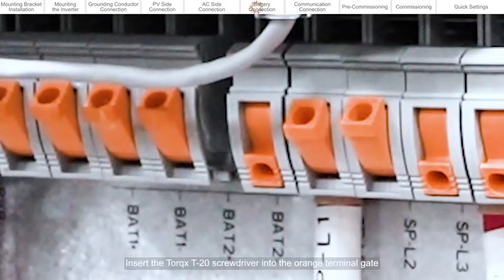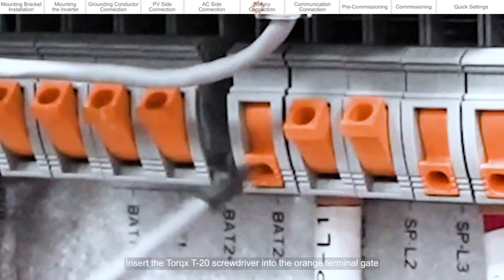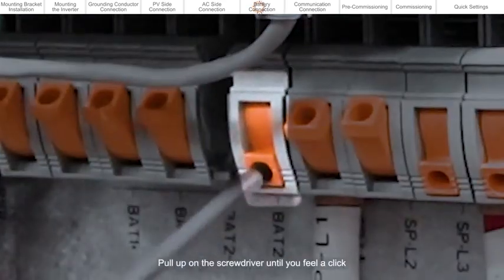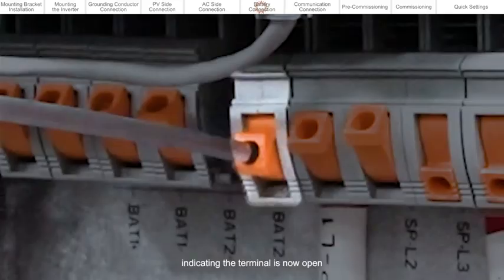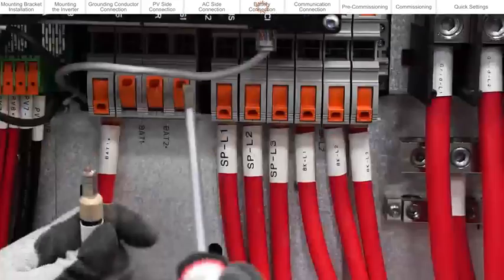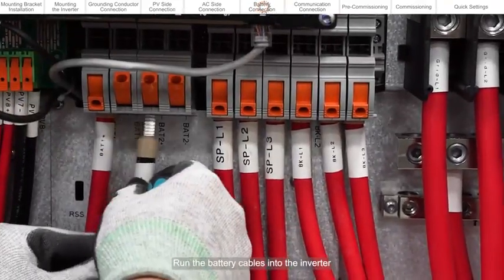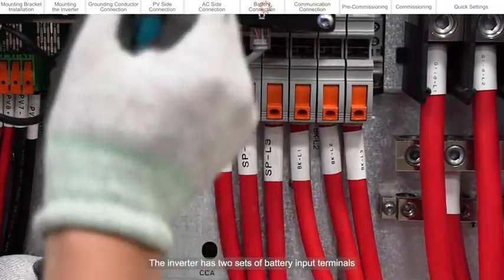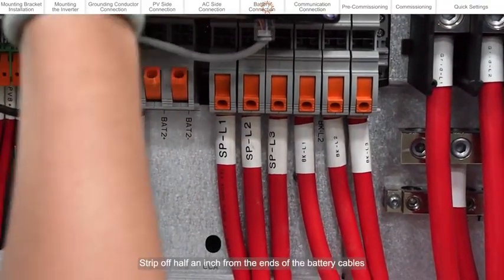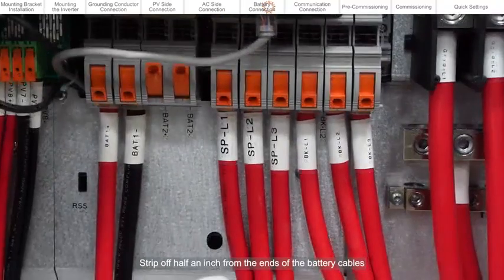Insert the Torx T20 screwdriver into the orange terminal gate. Pull up on the screwdriver until you feel a click, indicating the terminal is now open. Run the battery cables into the inverter. The inverter has two sets of battery input terminals. Strip off ½ inch from the ends of the battery cables.